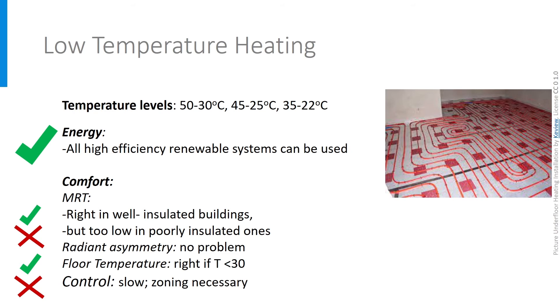So, even if the needed heat as calculated with the heat balance is supplied, residents may feel very uncomfortable because of the too low MRT. That is why it is strongly recommended to apply low temperature heating only in well insulated buildings. Another source of discomfort when applying low temperature floor heating may be the inertia of the system. If you feel cold and put the thermostat higher, it will cost a lot of time before the room air temperature increases, because of the mass of the floor and walls and a high share of radiative heat. So people have to get used to this. An appropriate zoning is also necessary to be able to control separately diverse rooms, like living room and bedrooms, otherwise rooms may be unnecessarily heated.